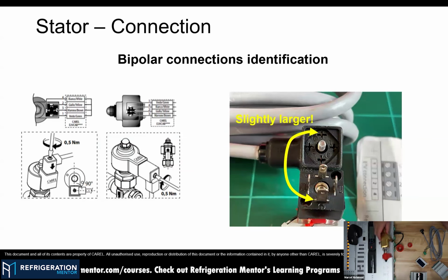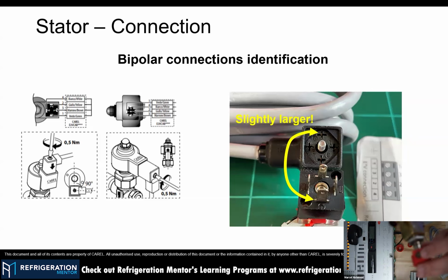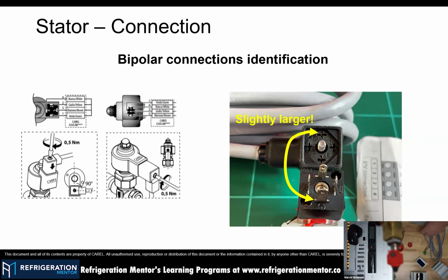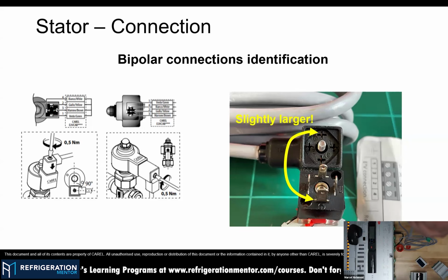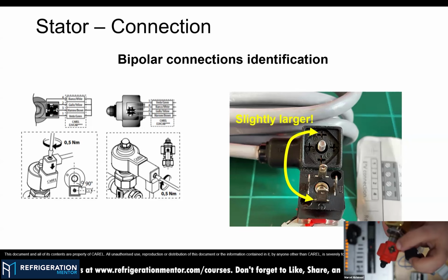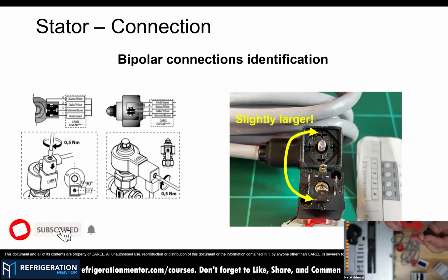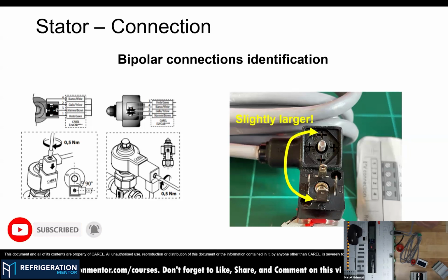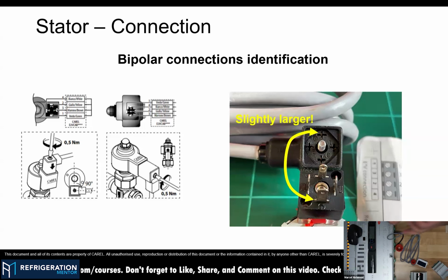And last but not least, the stator is a bipolar motor. You can see here that we have 4 terminal connections and they are identified. You should not connect them in any direction. We have a correct direction for installation. And I don't know if you can see in the camera, but we have a pin here that is bigger than the other. So if you don't force it, it will not enter. But I have seen multiple times, you are in a hurry, you didn't pay attention, and you forced it, and it will enter and deform the connectors. But this would not be the right way to install the valve.